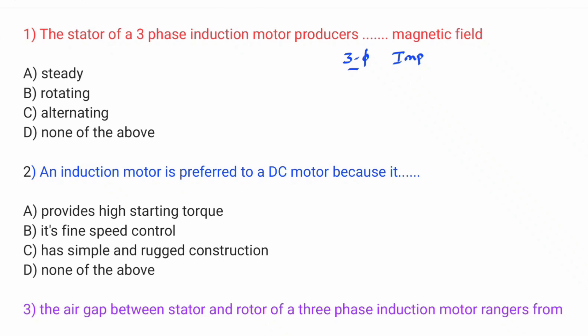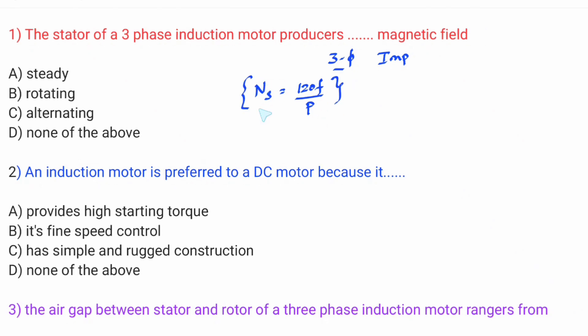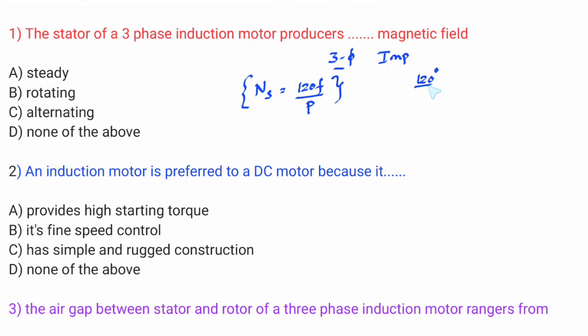For three-phase induction machines, the synchronous speed formula is Ns = 120 × f / P. This Ns is the synchronous speed — the upper speed. With three-phase supply applied, there is a 120-degree phase difference and 120-degree physical displacement, which produces a rotating magnetic field. The stator of a three-phase induction motor produces a rotating magnetic field at synchronous speed.